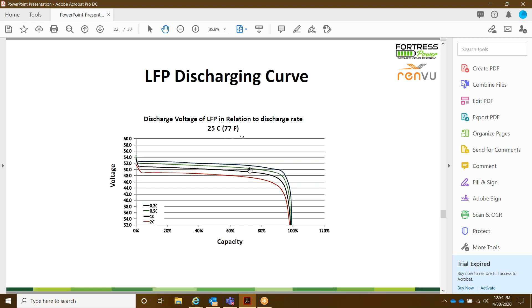Next, I want to bring up the temperature impact on lithium iron phosphate. So LFP has a very broad discharging and charging temperature. It can really range from 32 degrees Fahrenheit to 130 degrees Fahrenheit. And you can see here that the stipulation with temperature is, as it gets colder, even to -4 degrees Fahrenheit, it doesn't stop charging or discharging. It is the rate of the charging or discharging which is affected. So although our batteries are primarily an indoor unit, which we really do recommend, should it be somewhere where it can be subject to colder temperatures or maybe warmer temperatures, the broad discharge and charge range will help, but at the same time, it'll be good to know that the rate of the charging and discharging will just be slowed down.